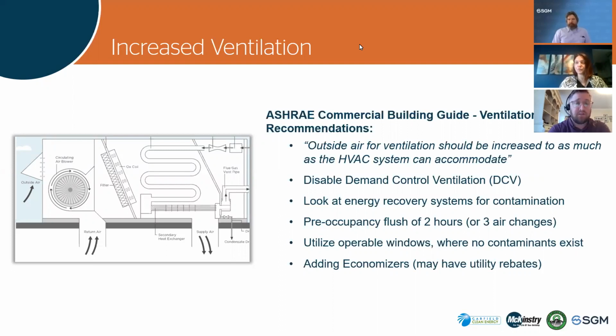Some side notes on this: if you have demand control ventilation, i.e. CO2 sensing, go ahead and disable that or override set points. You need to look at your energy recovery systems, make sure they're not mixing contaminated air. Additionally, there's a recommended pre-occupancy flush. And what this means is disabling any optimized startup routines in your systems and flushing the building with outside air before occupants are there.